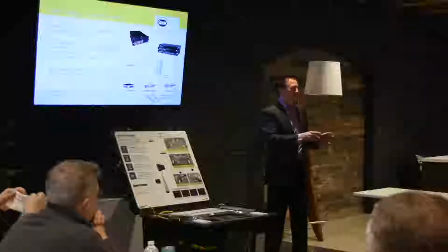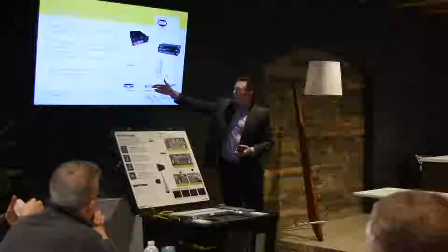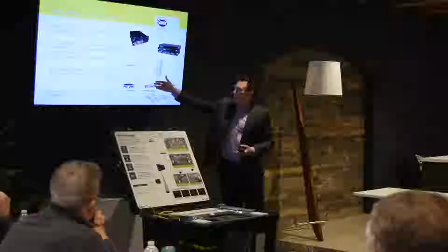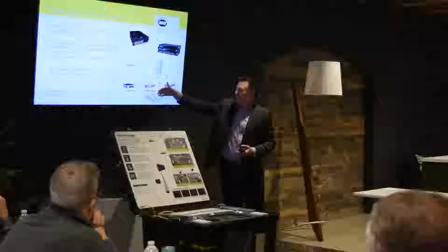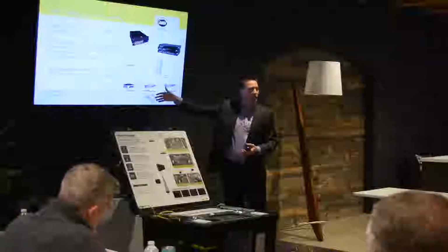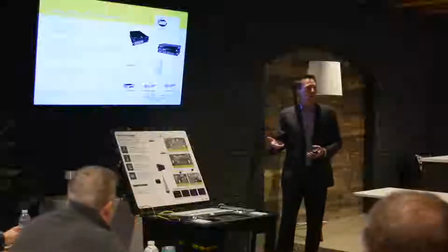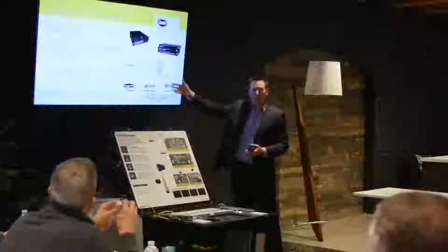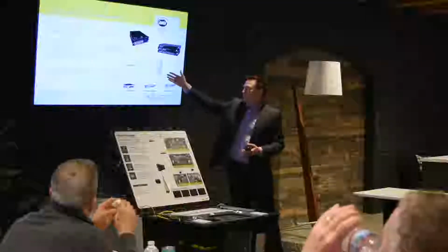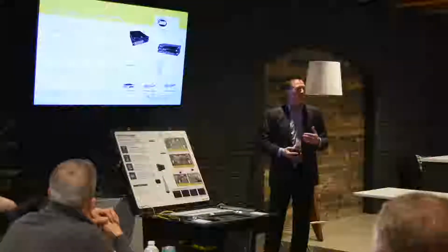So imagine being able to use a UPS that is attached to your switches, so that if it needs emergency power, the UPS is what's powering these lights. You don't have to have batteries in every single fixture, and batteries only last so long, just like your cell phone or anything else. You don't want to have to go around replacing batteries all the time in your facility. Instead, it's in one centralized location, and it makes it a very simple thing to maintain.